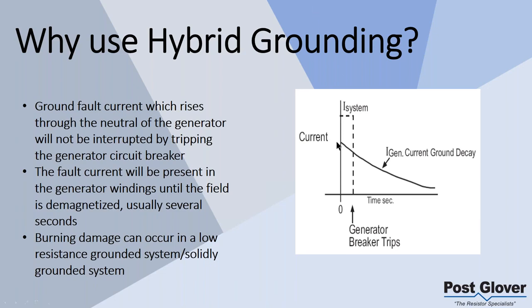The reason is because this is your system, this is your generator current, and your system is going to trip here when it sees this elevated current, okay? And so your system is no longer active in one sense because you're trying to shut down, but you're not shut down yet. You're still winding down, and you're winding down with that fault. So that wind down period is going to actually create more damage. In fact, a study was done that showed that the majority of the damage created in that type of fault came from the generator itself. So the point is that you're actually creating more damage after you trip than before.